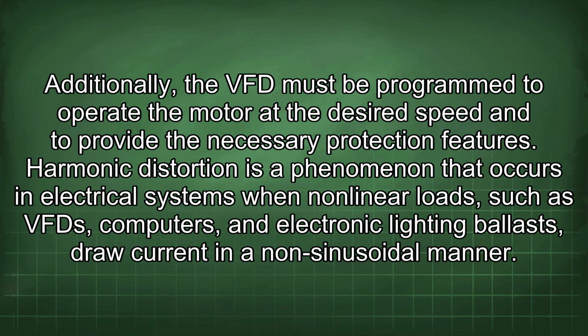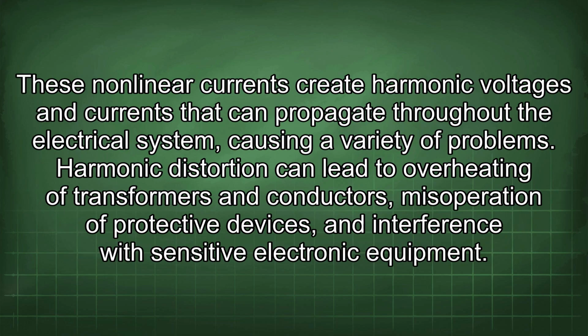features. Harmonic distortion is a phenomenon that occurs in electrical systems when nonlinear loads, such as VFDs, computers, and electronic lighting ballasts, draw current in a non-sinusoidal manner. These nonlinear currents create harmonic voltages and currents that can propagate throughout the electrical system, causing a variety of problems. Harmonic distortion can lead to overheating of transformers and conductors, misoperation of protective devices, and interference with sensitive electronic equipment.